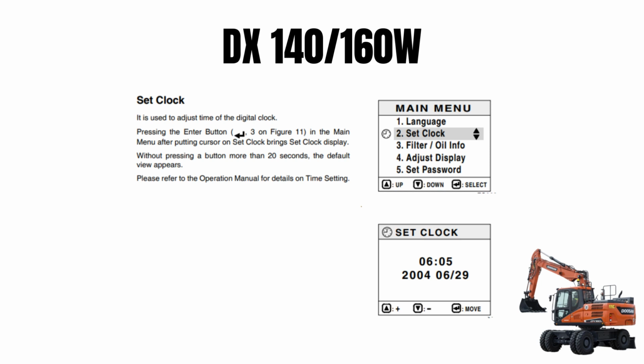Here you can see the clock, how you can adjust the clock. Here you will find this filter oil information. This mode displays the total operating hours of filter and oil. After changing the filter and oil, reset the operating hours, and then the operating hours until the next interval can be easily checked. From here you can set your maintenance schedules. It will display the total running hours of the machine from the last replacement of filters and oil, so it indicates to operators how many hours the machine has run since the last oil change.